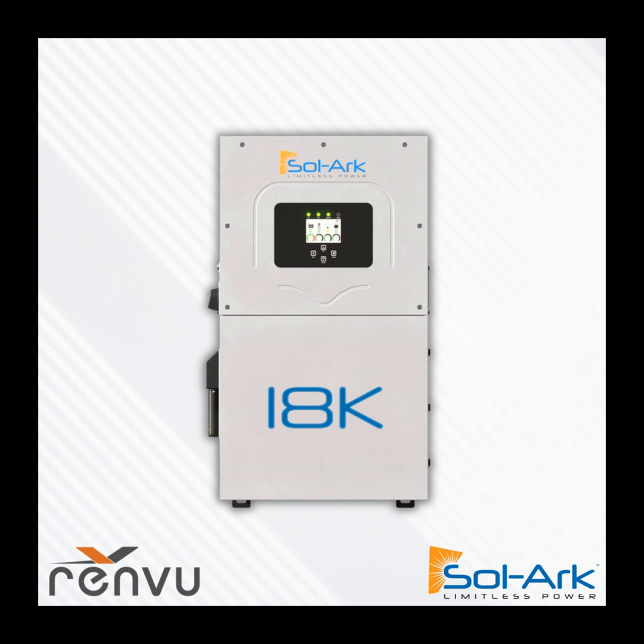So it's a very good combination: after you get to say 40 or 45 kilowatt-hours, just call it a day and add a generator, especially for a grid-tied system. But really, for the generator-less systems—the economic systems—the question is, is this enough to meet the customer's imagination of whole home backup? In my opinion, 20 or 25 kilowatt-hours is not enough, because the system would still require a little bit of daily grid use.